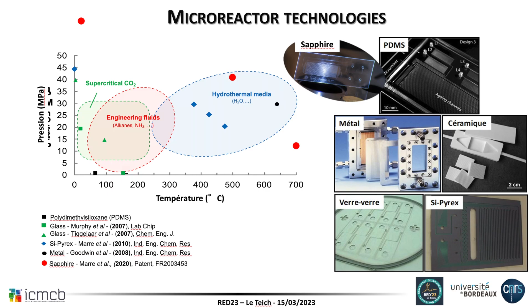So recently we have developed a sapphire microfluidic reactor that really covers all this range of pressure and temperature conditions. The interest is that you can go up to 700 bar, 700 degrees Celsius, all ranges of pH, completely neutral chemically speaking. So you're not going to have deterioration of the sapphire unless you use, and that's the way we make them, a mixture of sulfuric acid and phosphoric acid at 300 degrees Celsius. So mostly, even for hydrothermal vent conditions, we're good. They're going to be completely neutral to the environment we want to study.